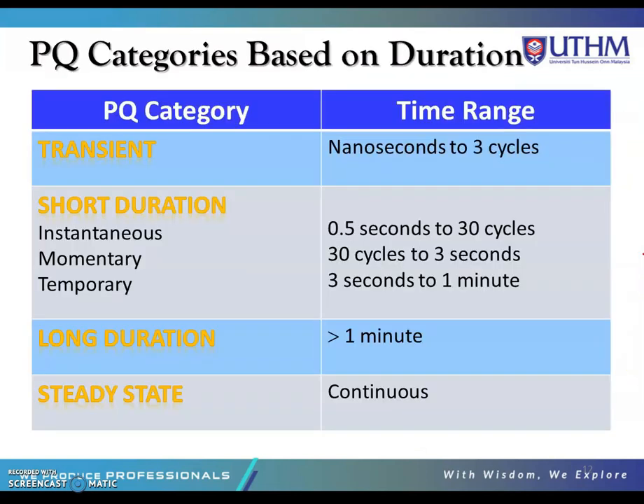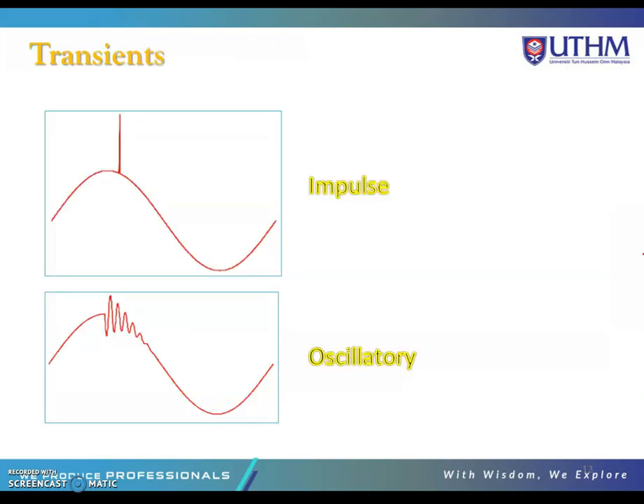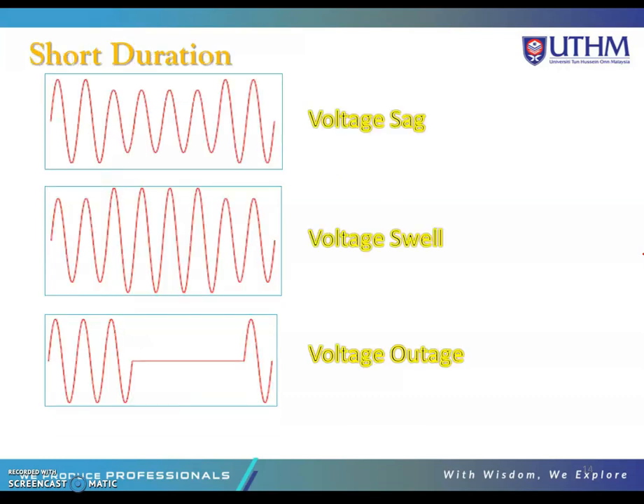Power quality categories are based on duration. Transient events last from nanoseconds to 3 cycles. Short duration events include: instantaneous (0.5 cycles to 30 cycles), momentary (30 cycles to 3 seconds), and temporary (3 seconds to 1 minute). Long duration events last more than 1 minute, and steady-state disturbances are continuous. Transients are momentary variations in current, voltage, or frequency and have impulse and oscillatory waveforms. Short duration events include voltage sag, voltage swell, and voltage outage.